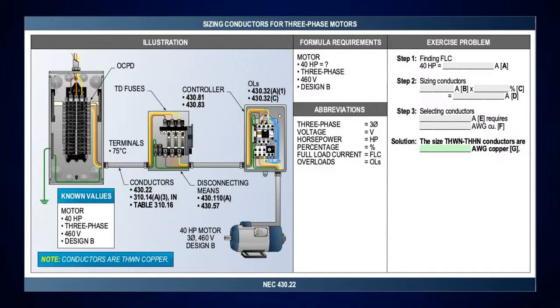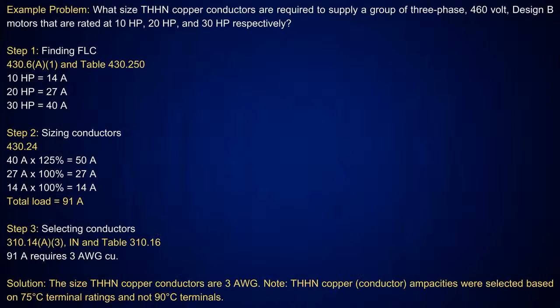He goes, "I was thinking, God dang, man, this is easy." And I said, "It's really not that hard once you understand the process." Like in here, you've got a 40 horsepower, 3-phase, 460-volt design B motor. Where are you going to go? Table 430.250. Every time I'm sizing my conductor and overcurrent device, I'm at one of those tables. And then I only have a single motor, so 430.22 says I have to take it at least at what? 125%. Then you do that, then you've got your amperage, then you go to table 310.16, find the next amperage size above it in the 75-degree C column, and there's your size conductor.